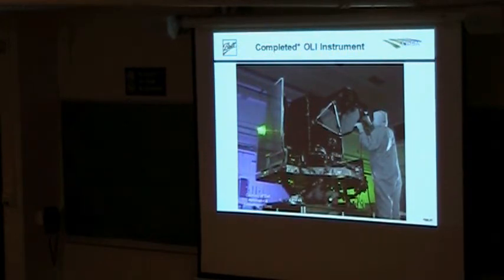Thermal engineering was a huge part of designing and building this instrument because of the type of temperatures we needed to maintain and the stability of those temperatures. The focal plane temperature variation is 50 millikelvin over the life of the instrument, so it does not change, and it needs to be that stable in order to get our radiometric performance of the system.